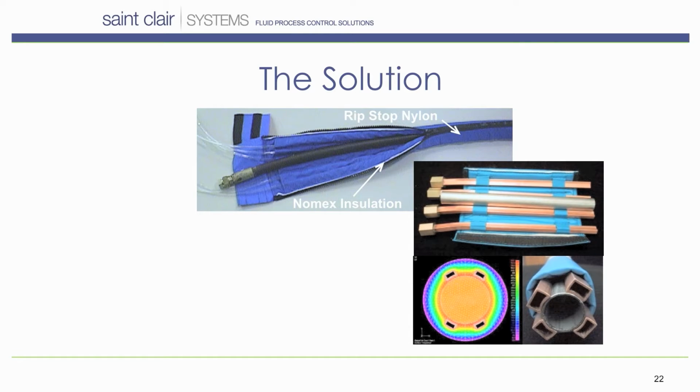So, in this instance, what we've done is we've taken polytubes and run them through tube pockets sewn into the inside. And then we circulate temperature-conditioned water or glycol through here to change the temperature of the air around the hose or the pipe or the device. What that does is the insulation isolates from ambient. The circulating water changes the temperature of the air around the device and creates a new ambient at or near the temperature of the sealer inside the hose or pipe.